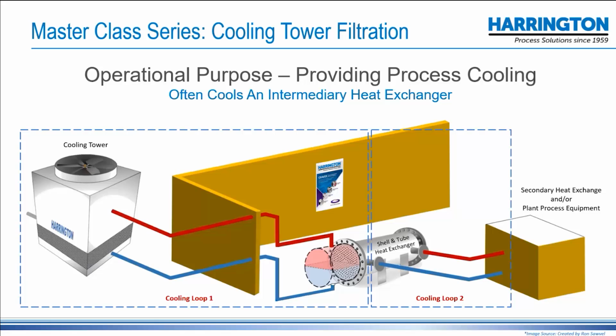You only smelled them as you went into the laboratory. Well, it was impractical to do that all through a conventional air conditioner, so we put a cooling system in, an evaporative cooling system, exactly what you see here, and then provided that cool water to an air exchanger, which was then further cooled by the conventional HFC air conditioner. And what that did was it allowed us to not expel tons of cool air up through the roof from the laboratory. So that's kind of an example of what you would use an air exchanger for.